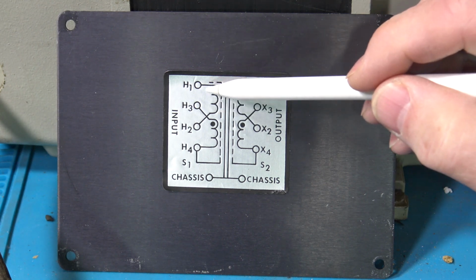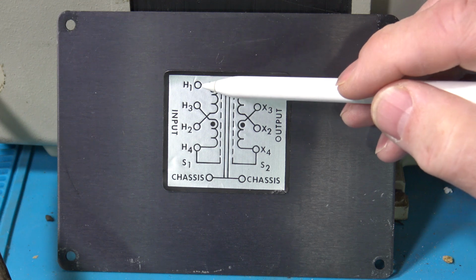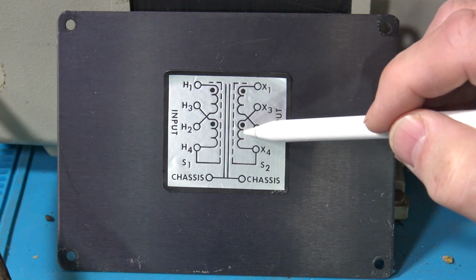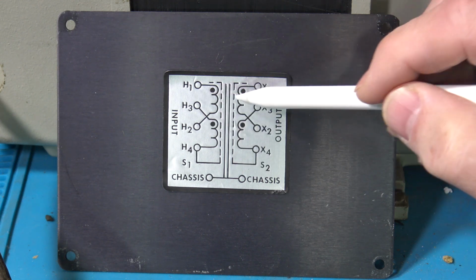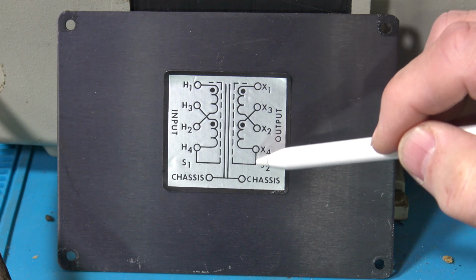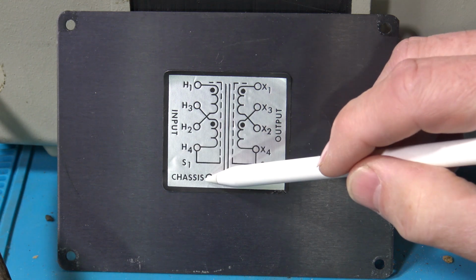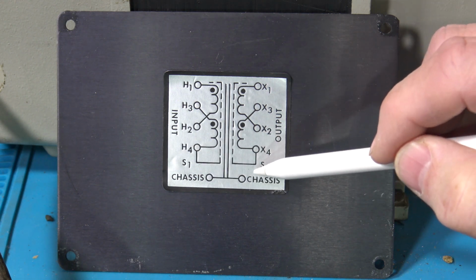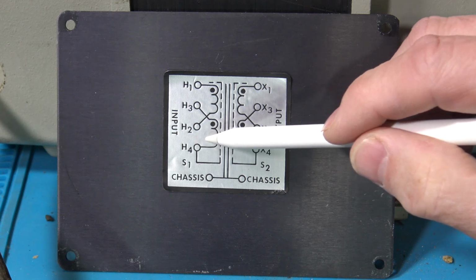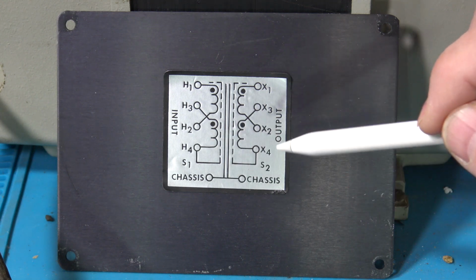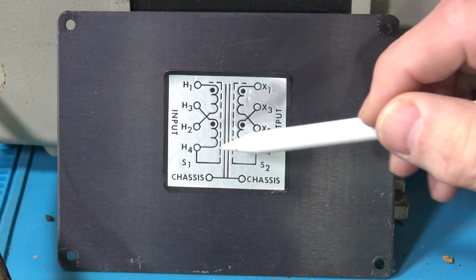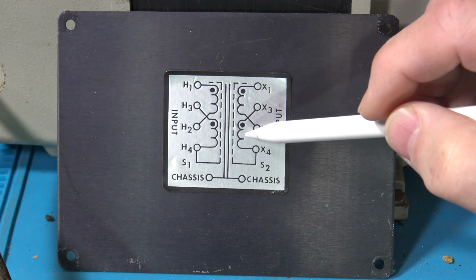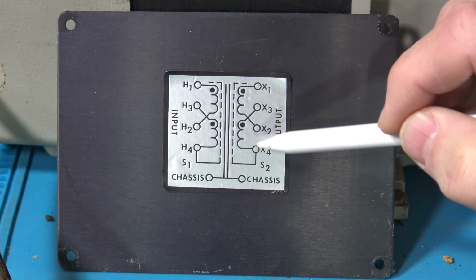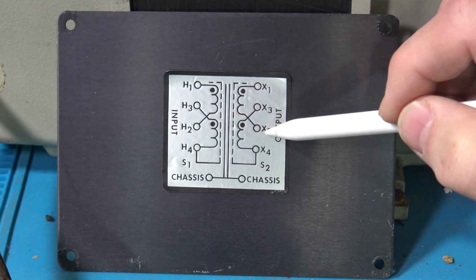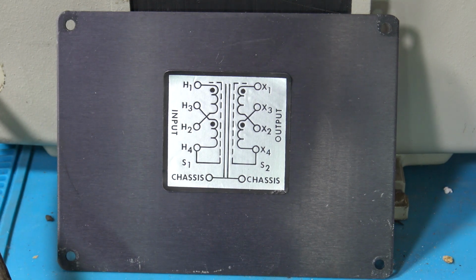After that, what we'll do is we'll HiPot. We'll make sure that each winding is open from the other ones. There's no continuity between the windings. Now, of course, these two will, because if they're tied to chassis, then we'll have these two windings both tied to chassis. Okay, so in that case, those guys will be connected, but we shouldn't have any other kind of connections. And we'll probably have to remove the screens just to make sure these guys are all open.